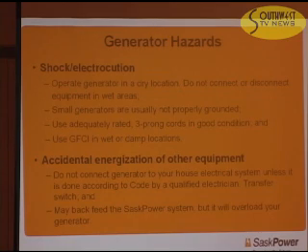Use adequately rated three-prong plugs. By adequately rated, I mean don't try to run a motor load on a number 16 extension cord — you should use a 14-gauge or 12-gauge cord for running larger loads. Use a GFCI when working in damp locations.